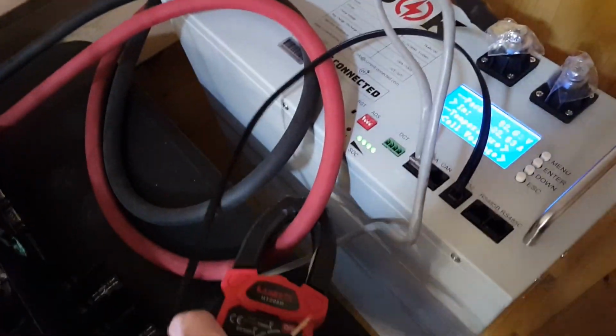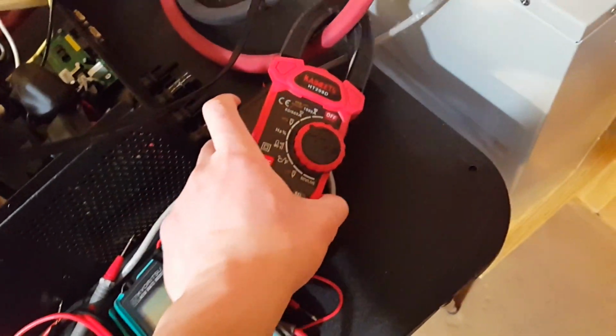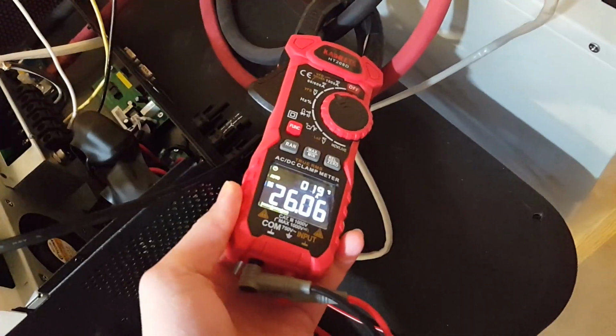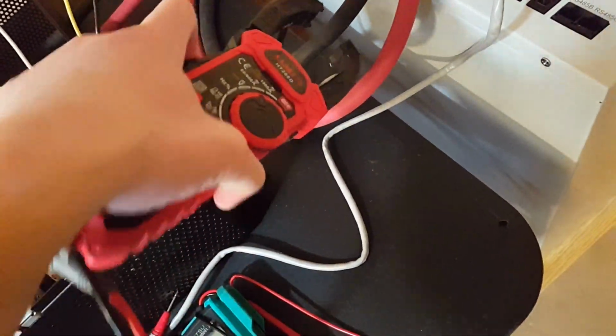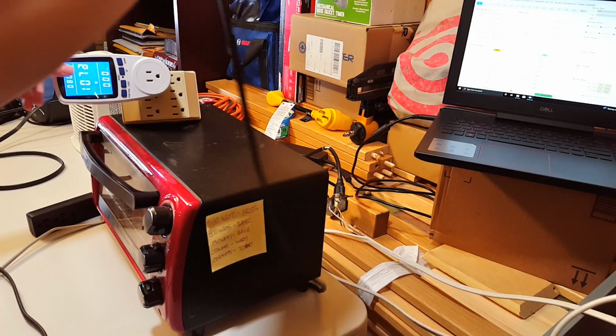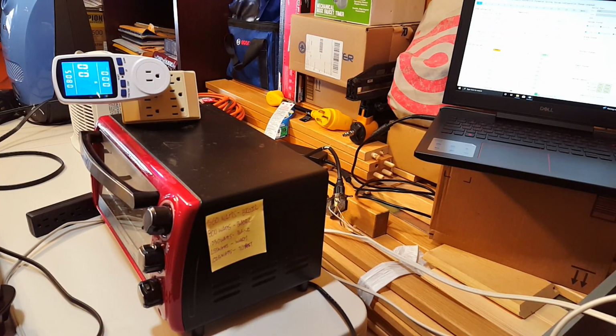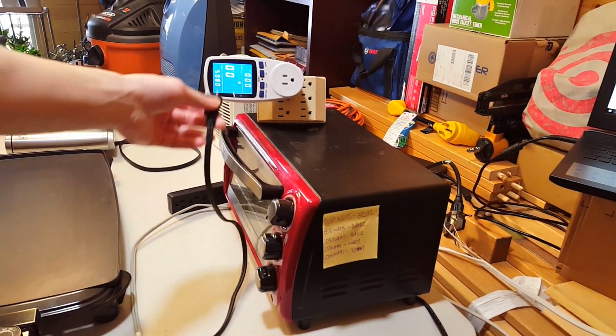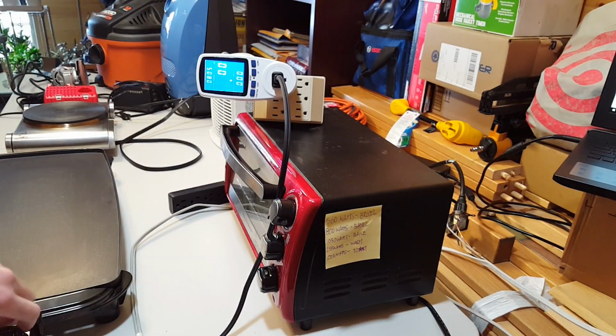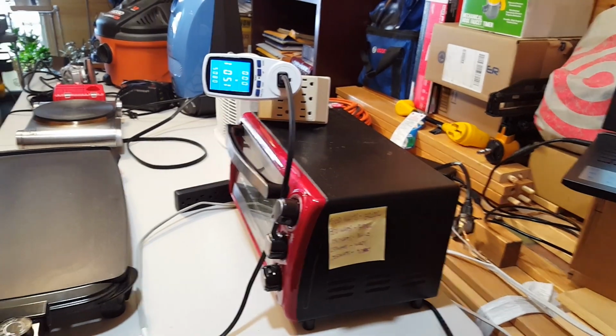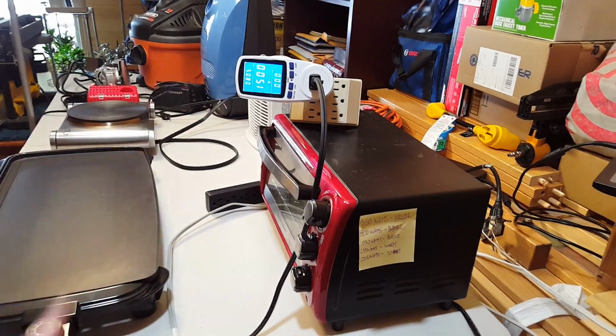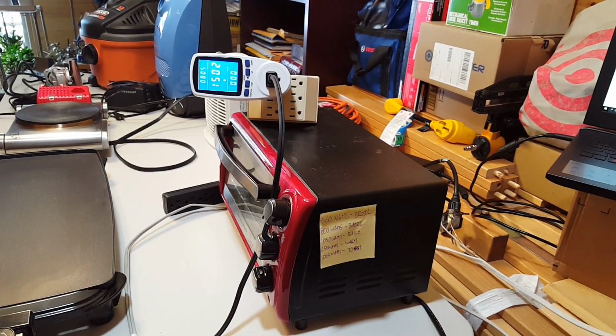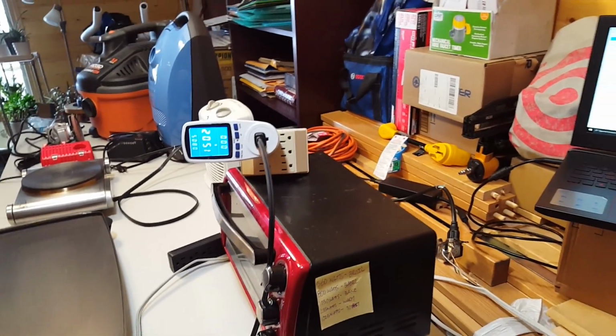Okay. DC amps, let's see. 21.6 on the one cable, and let's see the second, 26 on the second cable. Okay, that's the highest setting. Let's try a different load now. Let's try this frying pan over here on the side. Testing frying pan in battery mode as well. This frying pan on the left is doing 1500 watts, and that's fixed wattage, so you can't change the wattage. You can only adjust the temperature.